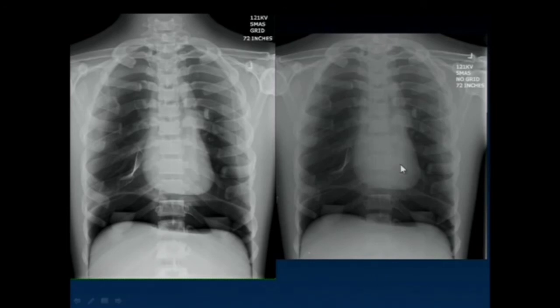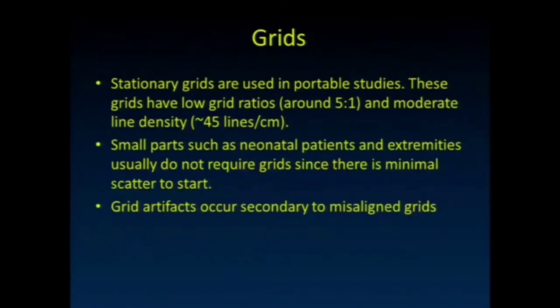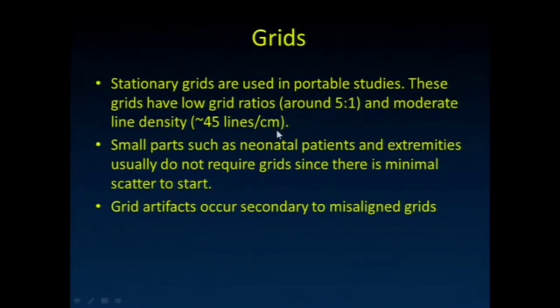Here is a chest phantom done with a grid in place, and here is the same phantom done without the grid. You can clearly see the reduction in contrast caused by all the additional scatter when the grid is removed.